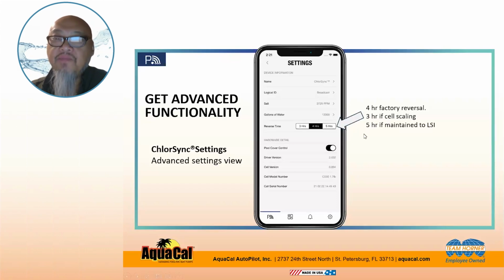On the other hand, if you're seeing the cell scale pretty frequently and you don't have the total control system or the ChemSync system, reversing to 3 hours so it reverses more frequently will help keep the cell clean. But the bottom line is, if you continue to maintain LSI, you'll have far fewer issues with the cell scaling up.